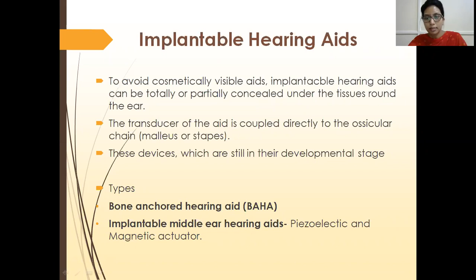The next is your implantable hearing aids. To avoid cosmetically visible aids, implantable hearing aids can be totally or partially concealed under the tissues around the ear. So this is the meaning of implantable. That means it needs a surgery. Yes, the transducer of the aid is coupled directly to the ossicular chain, malleus or stapes. And these devices, which are still in their developmental stage, are of two types, which we use mostly: bone anchored hearing aids and MET devices, that is implantable middle ear hearing aids.